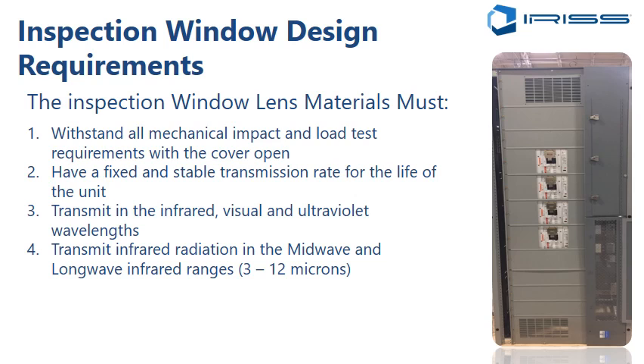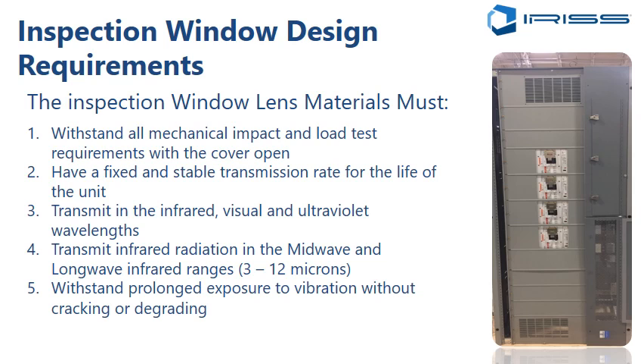They need to transmit infrared radiation in the mid-wave and long-wave ranges, so basically between 3 and 12 microns. Again, 20 years ago we were using mid-wave cameras, 3 to 5 microns. Then all of a sudden the long-wave cameras became much more popular, and now we're using long-wave cameras more and more. But you never know where the trends might go, and they might go back to using mid-wave cameras. So again, have a lens system that can utilize mid-wave and long-wave infrared ranges. Be able to withstand prolonged exposure to vibration without cracking or degrading. Again, these are test requirements of the OEMs and the standards like UL and CSA, etc.